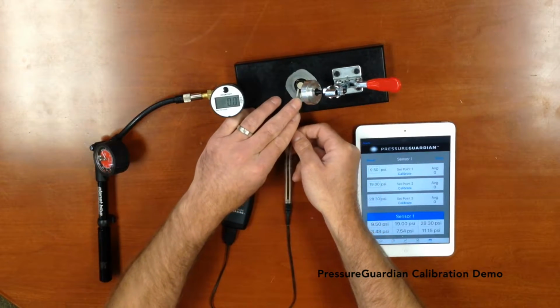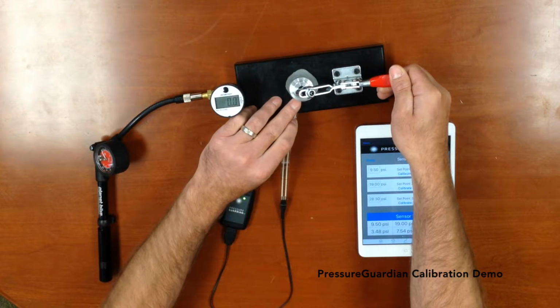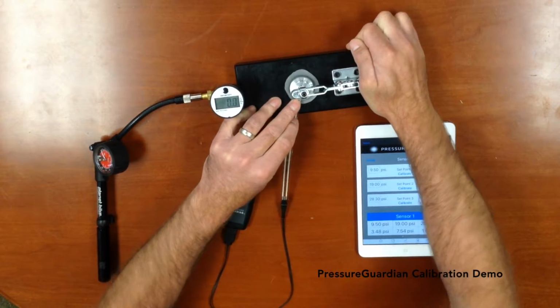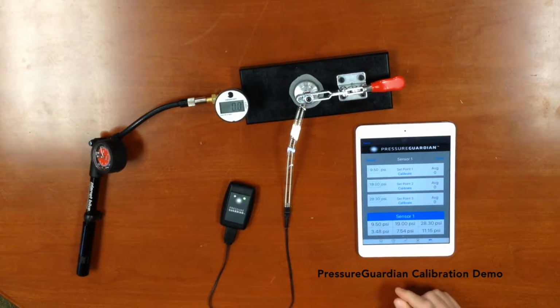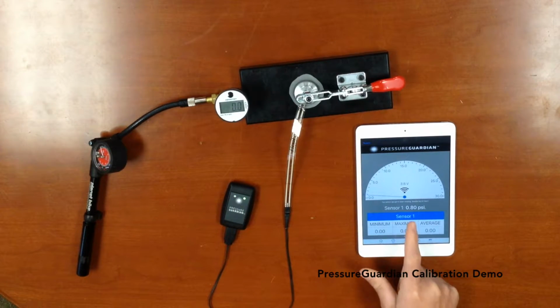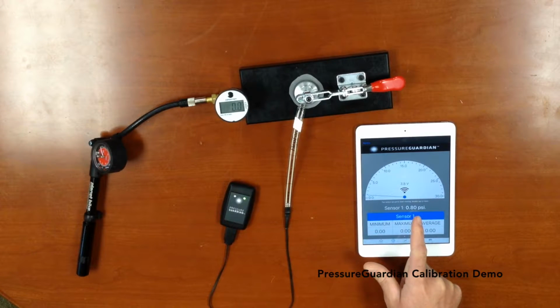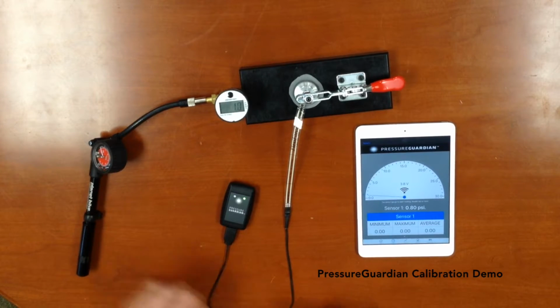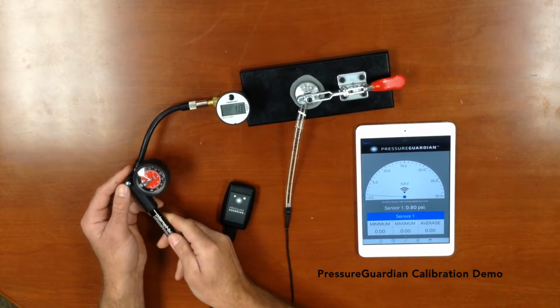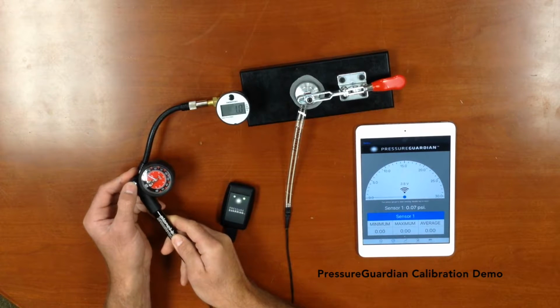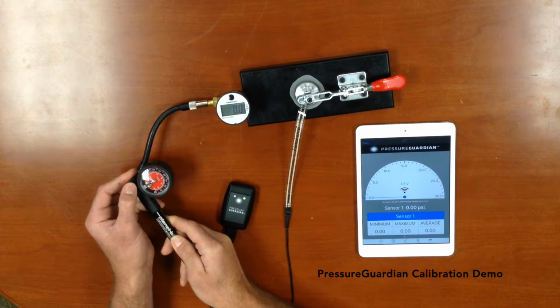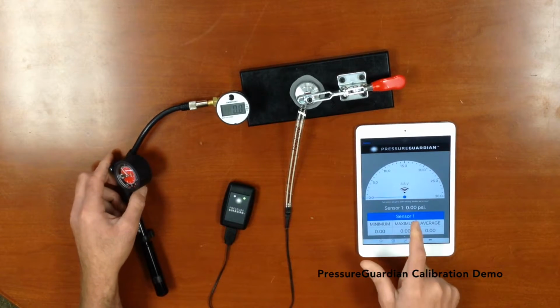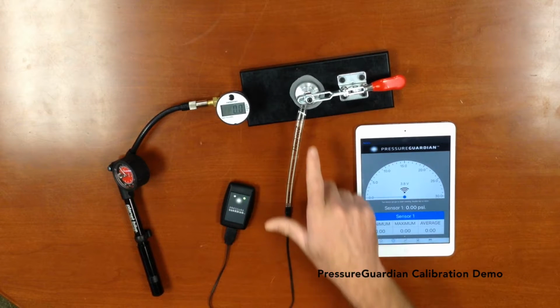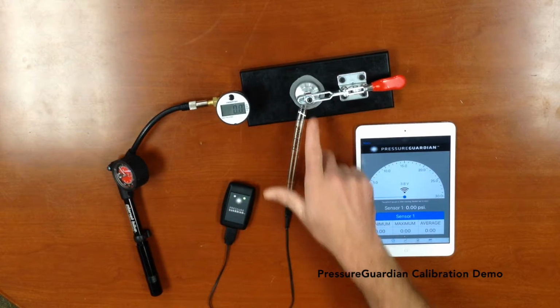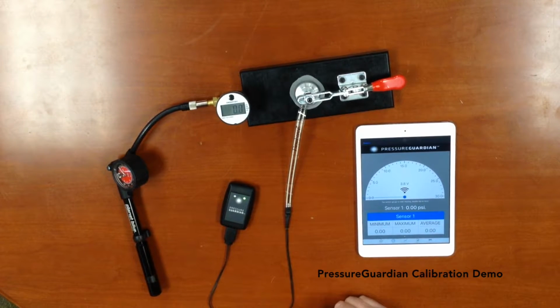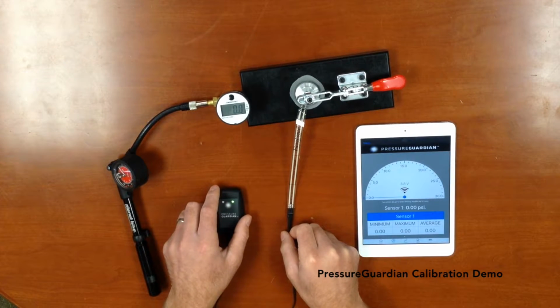Now we're going to clamp our sensor into the calibration jig, and we want to push the clamp down nice and firmly. I'm going to go back to my stats page, and you can see that I have a slight amount of pressure already built up in the chamber. So what I want to do is bleed that excess pressure out, and I'm just going to push this expulsion valve on the pump, and that should drop back down to 0 psi. If for some reason that does not drop to 0 psi, that may mean that we are pinching the sensor in the clamp. So we would have to re-clamp the sensor down into the jig.